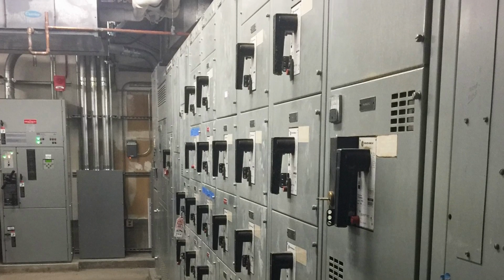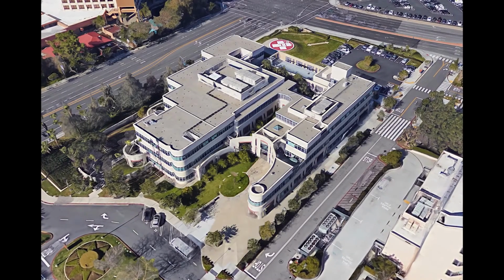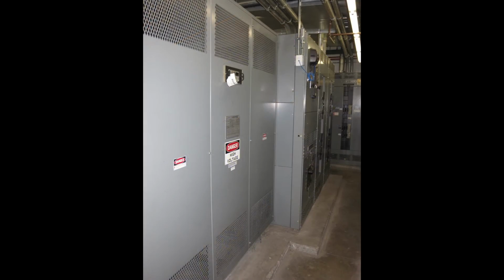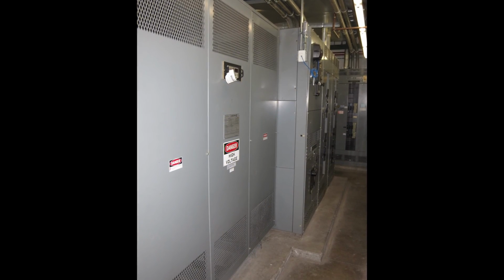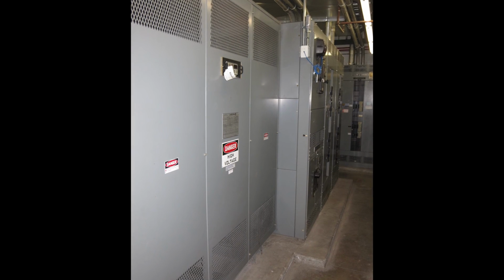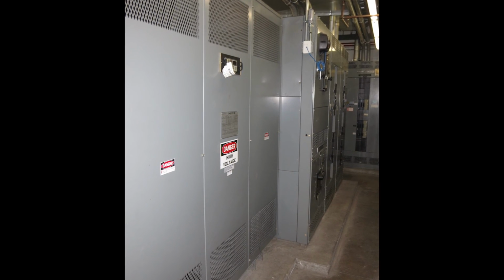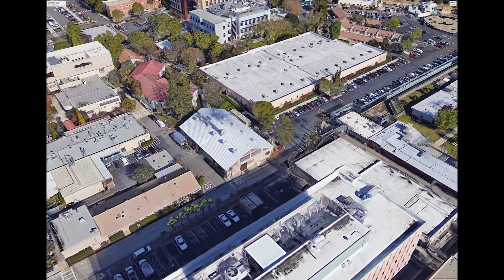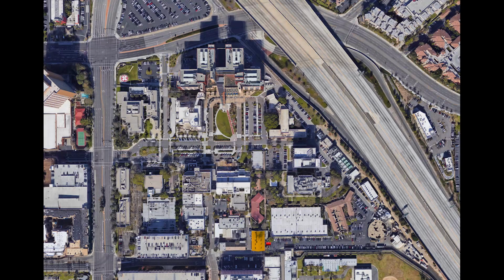The existing 5 kV switch in building 3 will be replaced with a 15 kV switch, and taps will be adjusted in the existing dual voltage transformer to facilitate connection of the Building 3 substation to the 12 kV system. A new SCE transformer, main switchboards, and transfer switch will be provided in Building 31. New duct banks and manhole for proposed SCE switches and replacement of the existing 750 kcmil feeder with a new 1000 kcmil feeder by SCE will be coordinated to minimize interruptions and energize the 12 kV system on schedule.